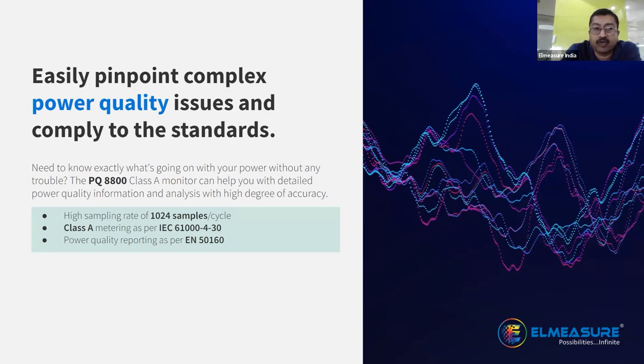So with 1024 samples per cycle, you can pinpoint and find where the problem is, where the flicker is, where the surge is, where the spike is, and how the harmonics are behaving in the industry. You can also use it as a check meter with respect to the tariff meter installed by the utility. Some of the features we built in along with that: it can be a midnight snapshot, or some of the load survey details that are part of the product, but can be used as a check meter with the utility also.